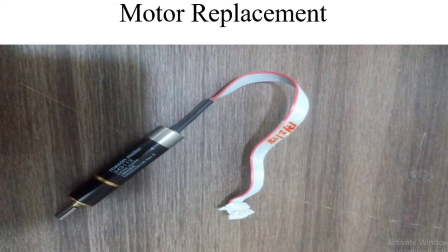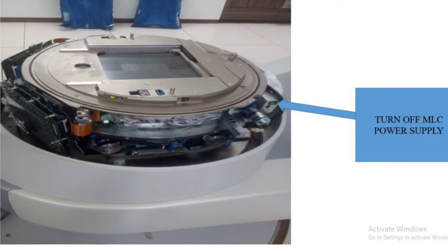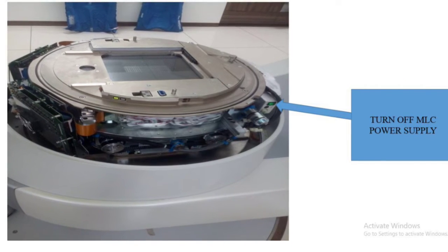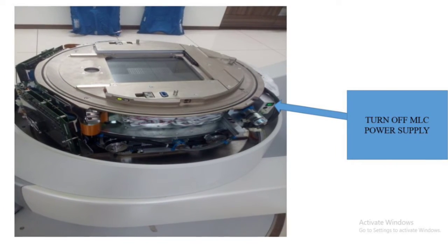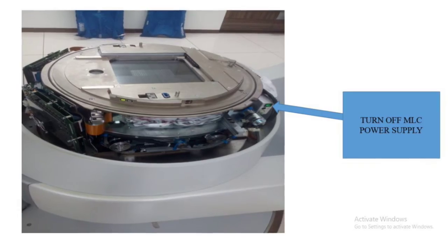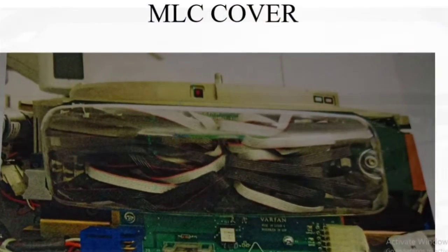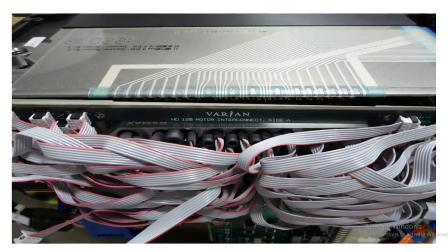First we have to retract the carriage completely so that we can easily access the motor area, and then we have to turn off the MLC power supply after retracting the carriage. Then you have to remove the MLC cover. Now in this picture you can see the MLC motors in the center and their connectors on the sides.